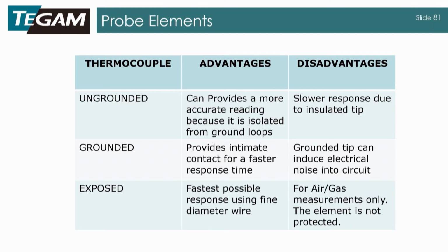And there's the grounded, pretty much what I just said there. It's a little more intimate. The one problem you have to remember with grounded tips is that you can induce electrical noise into a circuit because you're using a thermocouple and it has that millivoltage difference. That grounded tip now can have an electrical effect on the thing that you're measuring, or vice versa. The thing that you're measuring may have an electrical effect on your instrument.